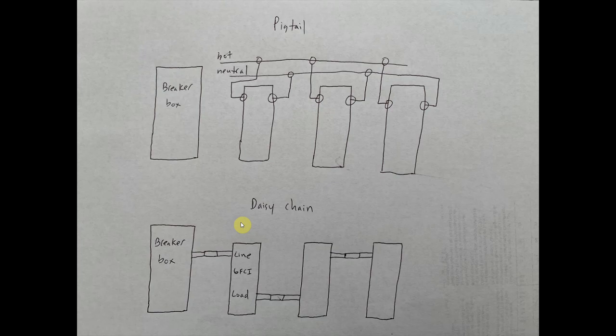In a daisy chain normally you're going to have a lot of wires in the box. So typically it's going to be six wires. If we use this GFCI as an example, you're going to have the line side and the load side. For GFCI, the line side is always the side that's bringing power into the box from the breaker, so you're going to have your black hot, your white, your ground down here. And then for your load you're going to have another set of black, white, and grounds.